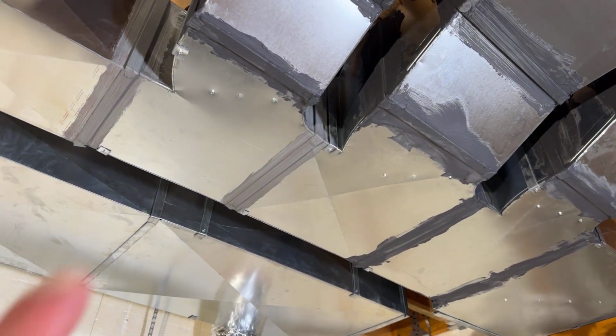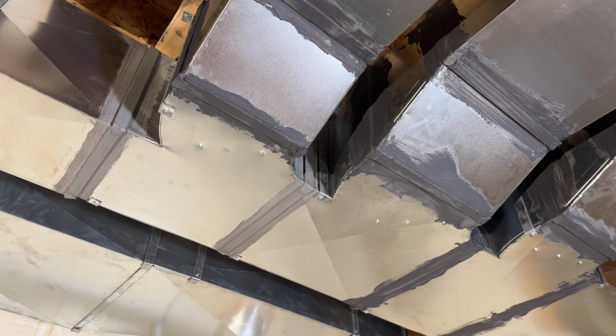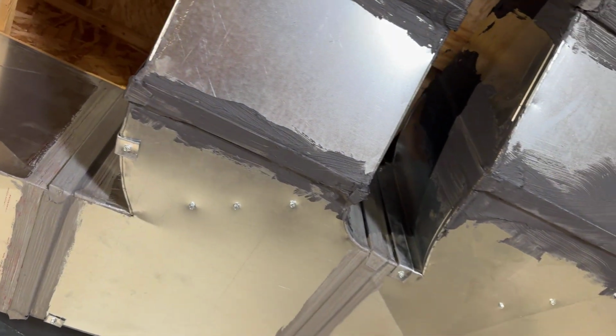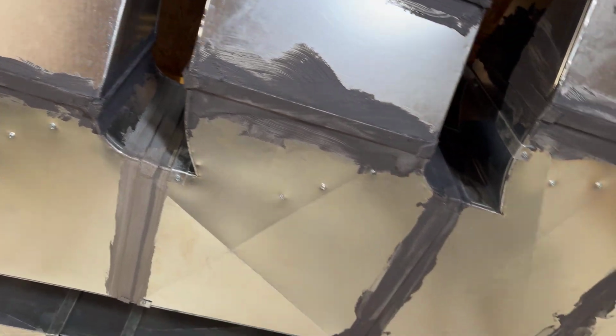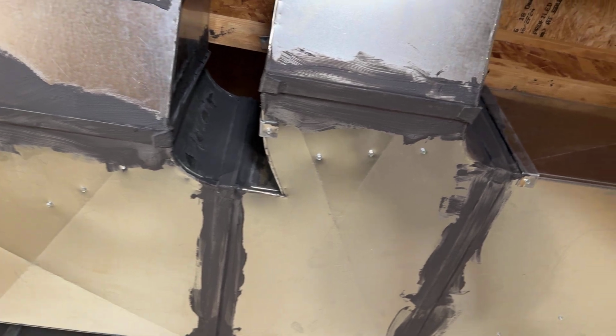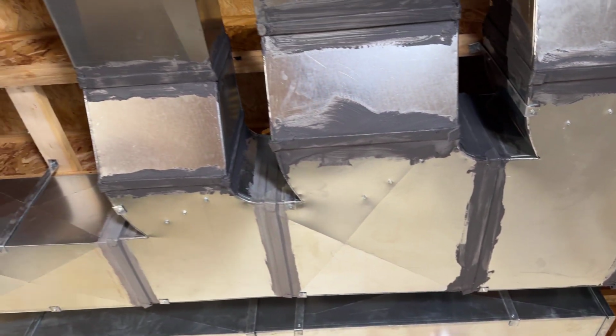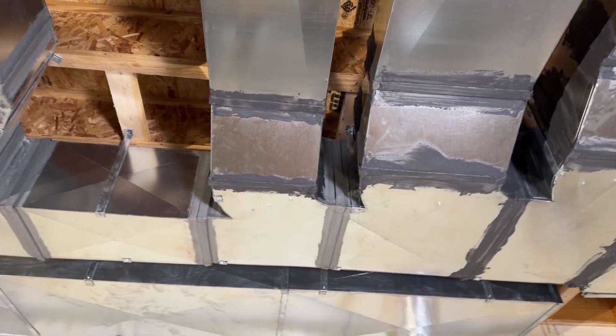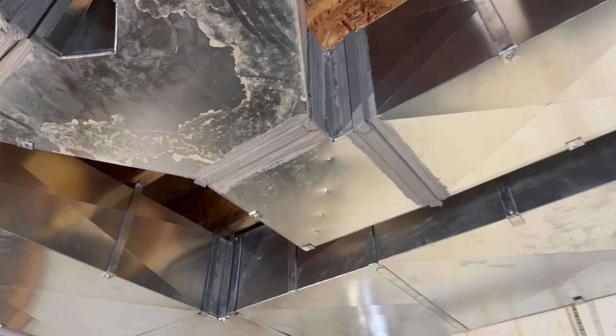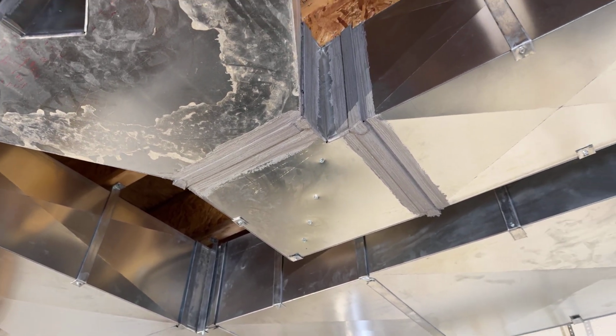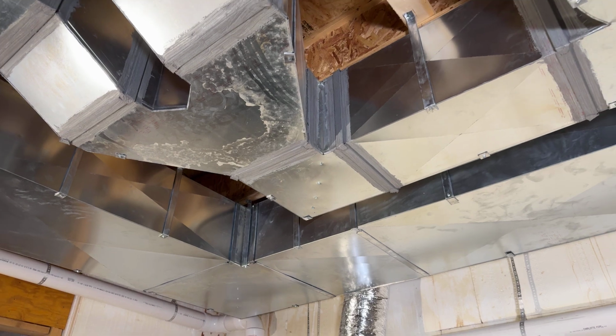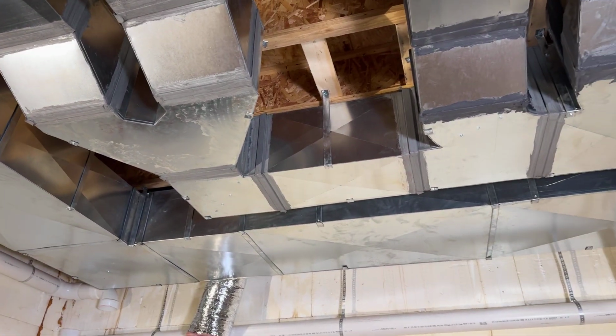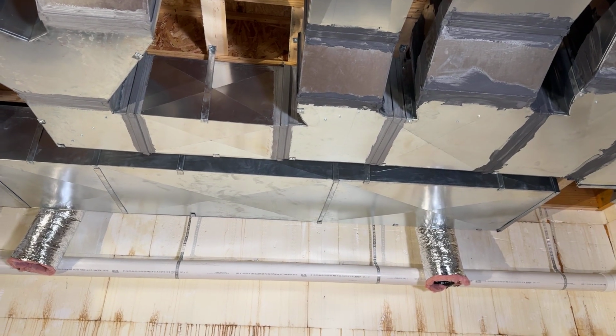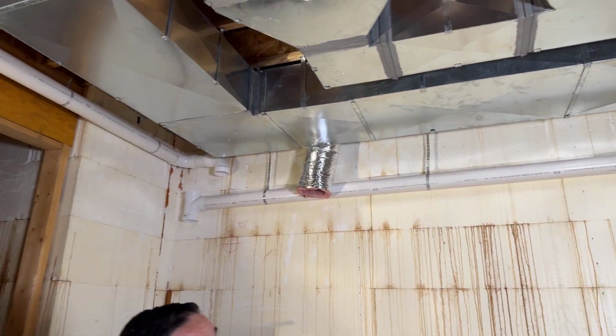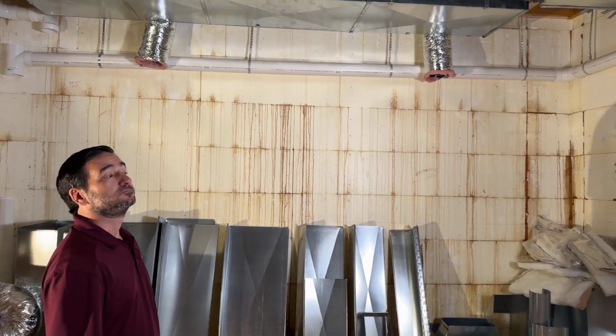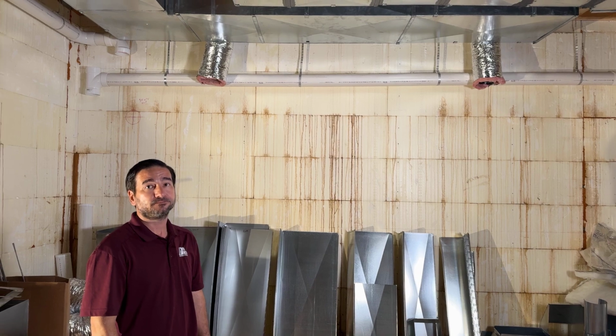So Richard, what are we looking at up here in those little washers or screws? What are those? Right. So when you talk about a 90-degree turn on a piece of duct, most people want to think that a duct fitting that has a round back or a radius back or throat on it would be more efficient. But actually what we find is that if you put turning vanes in the duct system or in that turn, it greatly reduces the friction of the air trying to go around that turn. So that is turning vanes, which is essentially just pieces of metal that are curved, and there's a series of them. So as the air is coming down the chute, it helps direct it where we want it to go. That improves the airflow without the need for making radial turns and sweeping longer turns.